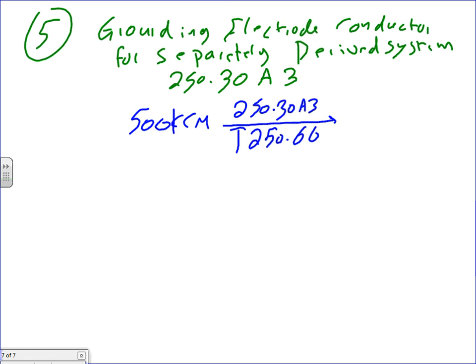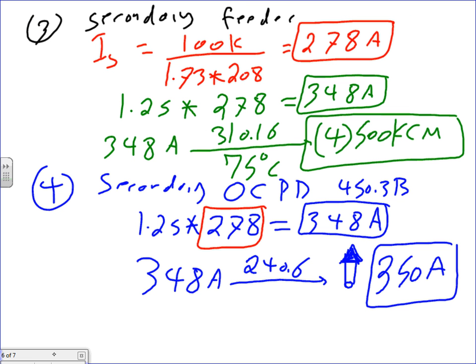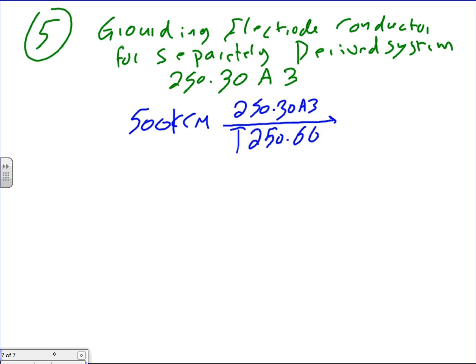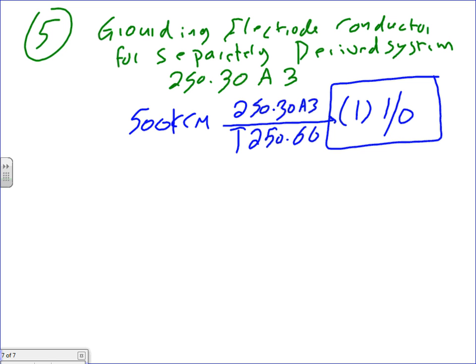We sized them, didn't we? The secondary feeders. We size the grounding electrode conductor for the separately derived system based on the secondary conductors of the transformer, exactly like a service. We do the same thing as for a service. Okay, what size did you come up with? 1 aught, one conductor, 1 aught. Does it have to be insulated? No, copper bare.